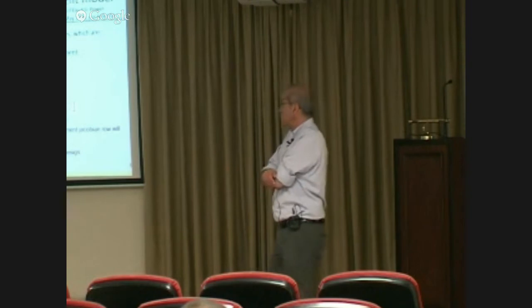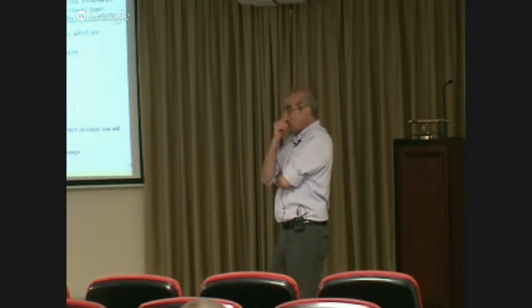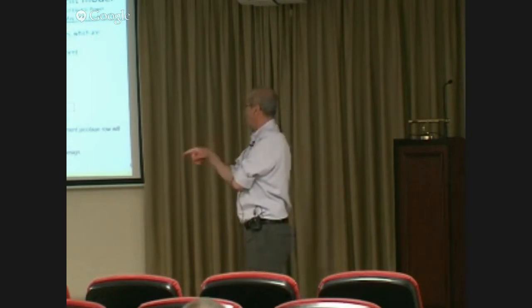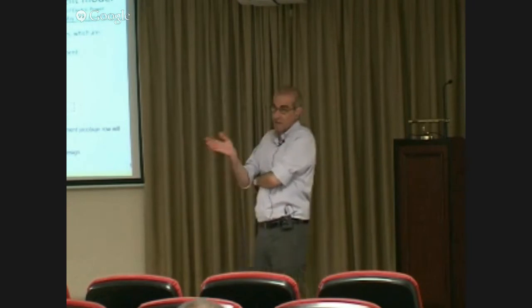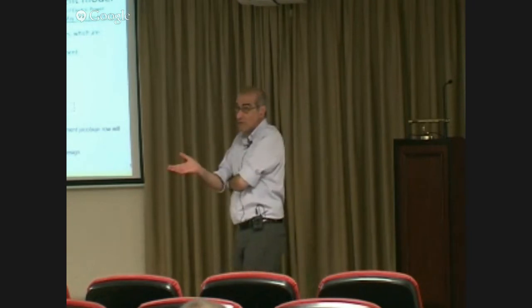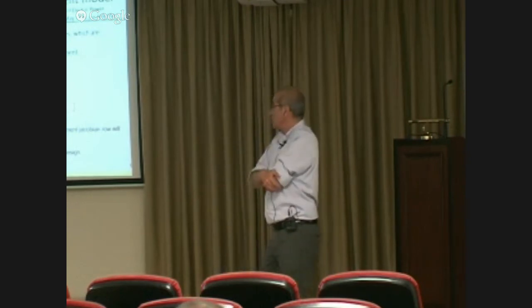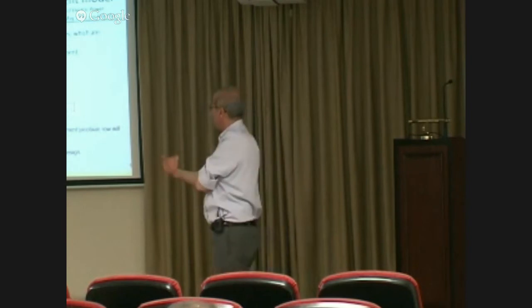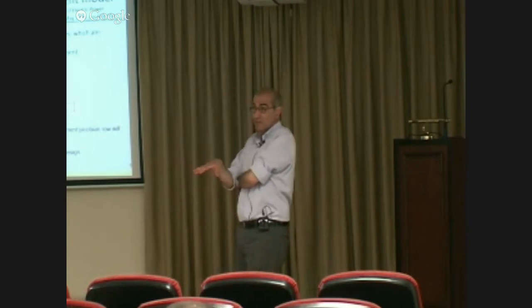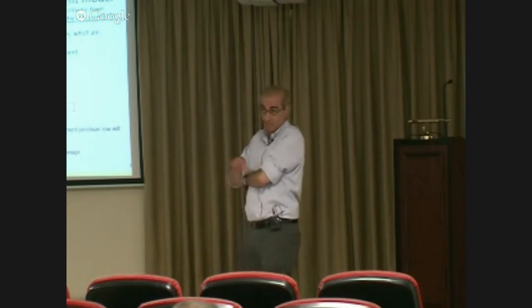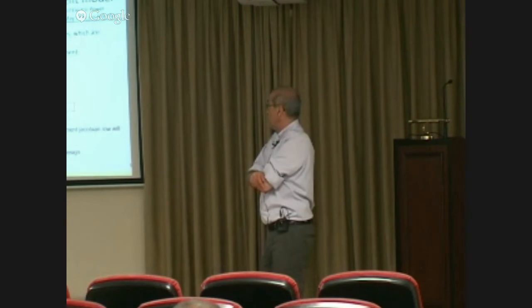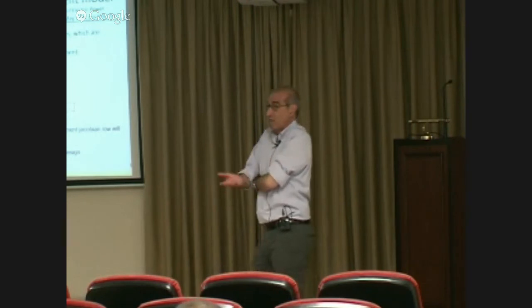Now, leverage measurements are sort of like stealth critical measurements. They behave like critical measurements, but they are not critical measurements. So when you go through the tests to identify critical measurements, they are not going to pop up, because they are not really critical. In fact, when you remove them, the system will still remain observable. But when you do the state estimation, they behave like critical measurements, meaning if they carry bad data, they will bias your estimate, but they are not going to allow you to detect it by the statistical techniques. And how do they show up? How many are they? Where do they show up in the power system?